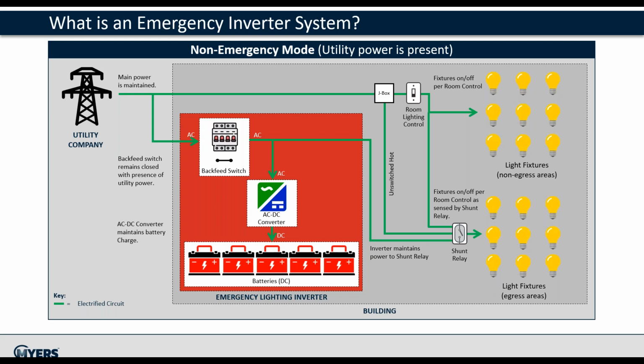On the lower right side, there's a shunt relay which performs three functions. First, it provides a mechanism of control for the light switch to turn on and off the egress lights. Secondly, it monitors the unswitched hot to determine when the incoming utility has been lost. And third, with the loss of power, it provides a bypass line for emergency power to feed the loads when the utility has failed.